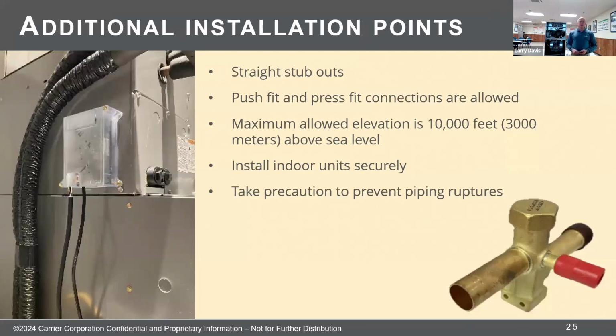All of our coils and units on the service valves are going to start coming with a straight stub out versus the swedged stub out. That allows for push fit or press fit fittings. If you want to braze that, you can still braze it, but it'll have to be swedged to make a braze connection there. If you're going to swedge it, don't use the hammer and swedge tool. Use the clamp and the crank swedge tool, so you're not beating the daylights out of your tubing or the fitting. I don't know, but I'd recommend swedging the fitting if it's me.